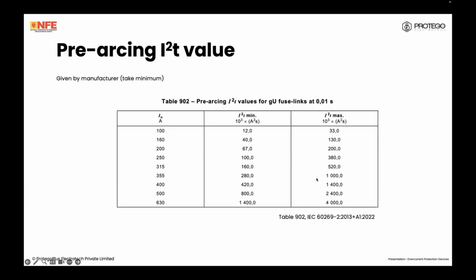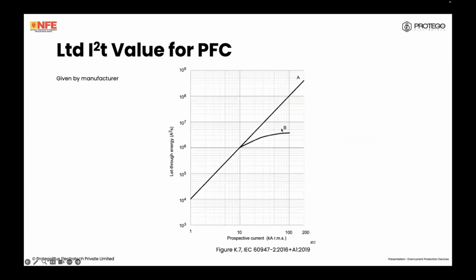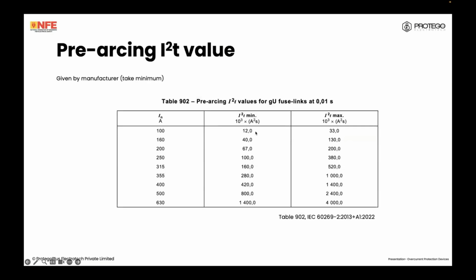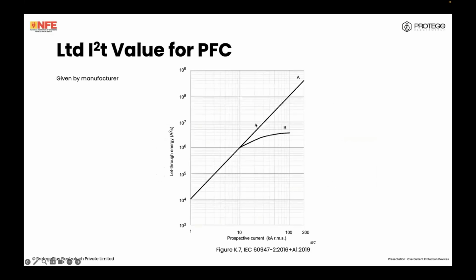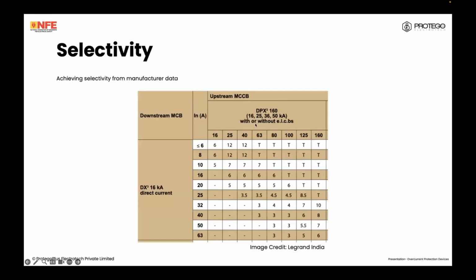So say for a gU fuse link, 100 amperes, the minimum I squared T it is going to release, pre-arcing, is going to be 12. Now there's also a maximum. We have to take the minimum because we have to assume the most onerous conditions, which is the lowest value at which it will arc. So if we know that from this curve, the value of limited let-through energy is less than say 12, this is times 1000 amp squared seconds, then we achieve selectivity for this arrangement, plain and simple.